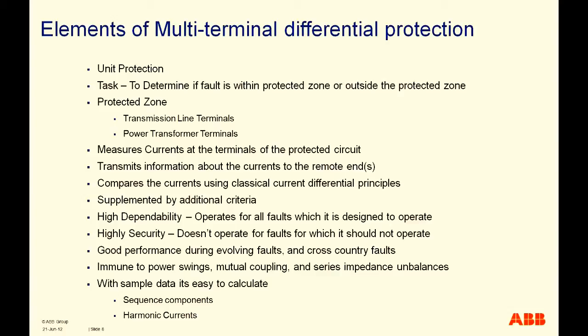In line differential protection, you can have obviously an element of equipment, the transmission line, which needs to be protected, but also in certain cases you have the power transformer within the protection zone as well. Having a power transformer within the protection zone of line differential protection imposes some more issues, and those issues need to be addressed, and we will talk about it.